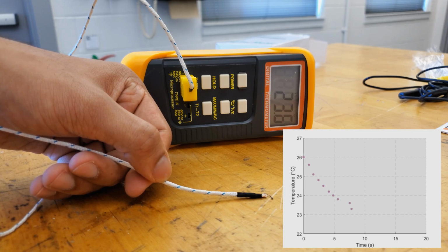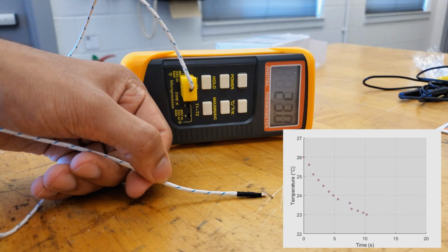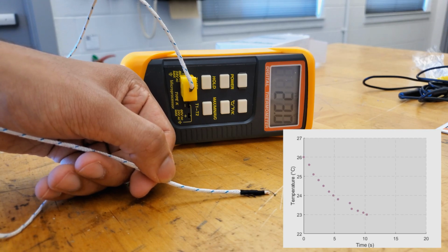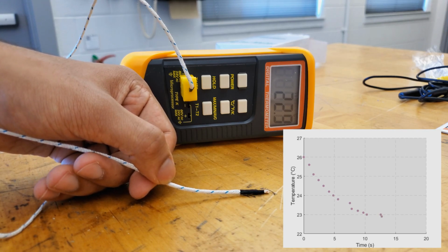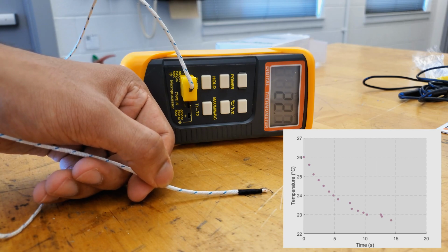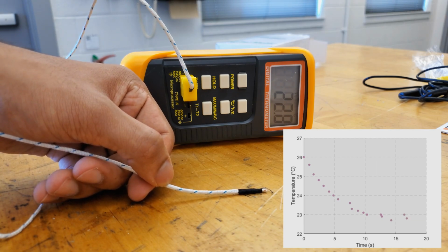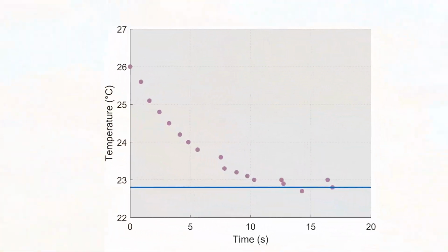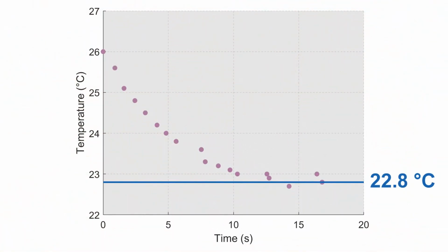Here, I'm plotting the temperature reading against time, and you'll notice that it takes about 15 to 20 seconds for the temperature to reach equilibrium before fluctuating about the equilibrium surface temperature. The fluctuation is not of much importance, but ensure that you wait at least 20 seconds before taking a measurement for the thermocouple probe to reach the surface temperature you're trying to measure.